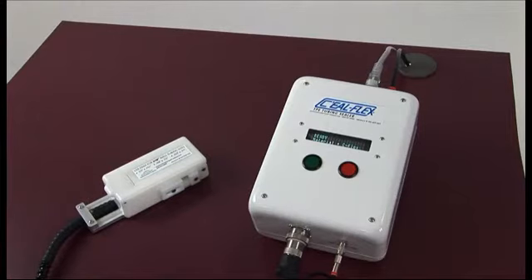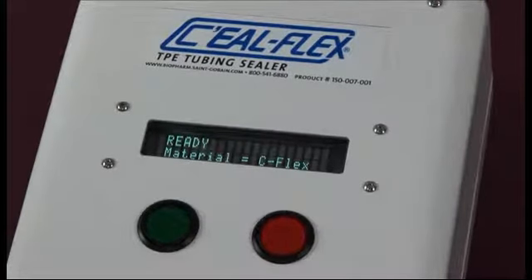When the machine is shipped from the St. Gobain plant in Clearwater, Florida, it's preset for the optimum settings on C-Flex thermoplastic materials. The settings are password protected, but you can make adjustments so that you can use it on materials within other thermoplastic families, for example from C-Flex to PharmEd or PVC.